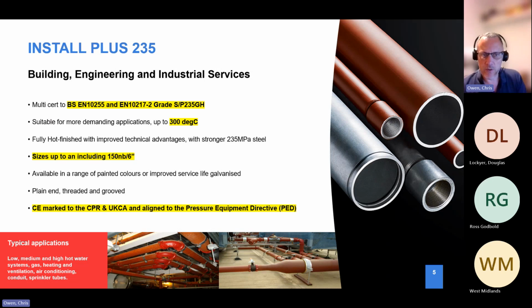That's why we also refer to the pressure pipe standards: 10217, which shows it's welded, and part 2, which shows it's suitable for elevated temperature use. Then there's the grade of steel used. In this instance it's a structural pressure grade, 235 minimum yield strength, with a GH quality designation, defining what additional product testing is carried out alongside the standard testing, showing suitability for elevated temperature use. This product is rated up to 300 degrees C.